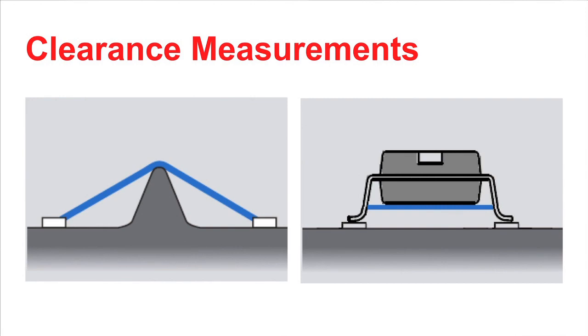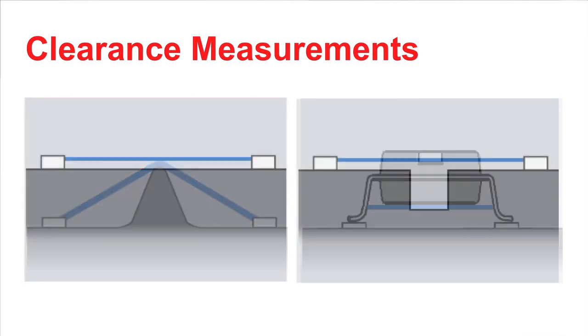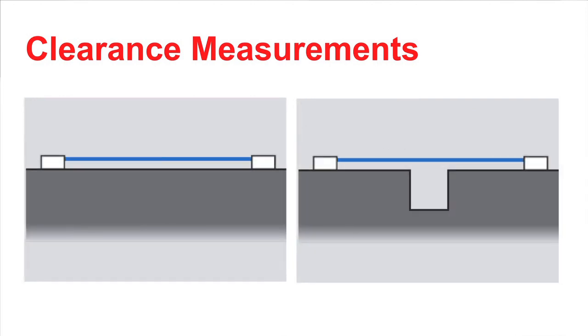Let's start by talking about clearance. Clearance is the shortest distance through air between two uninsulated conductors. These diagrams show different examples of how to measure clearance distance. Having adequate clearance for the voltage level and environment that you are designing for will prevent an arc over.